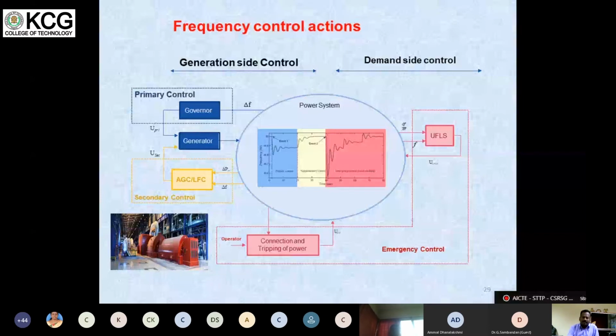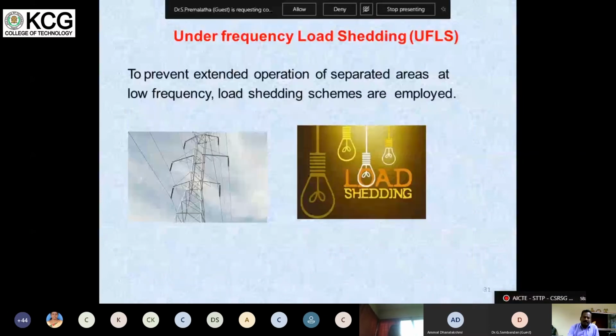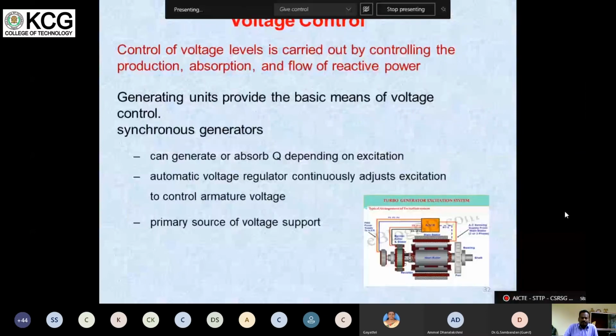And of course it is a frequency control system, and we have under frequency load shedding. Sometimes you may see load shedding also happens in our system, in our Tamil Nadu, any state. This is to maintain the frequency in the system. And of course, voltage control, already we have discussed, with the use of the excitation system and automatic voltage regulator. And using the tap changers, we can control the voltage in the system. So these are the two factors to be controlled, voltage and frequency.